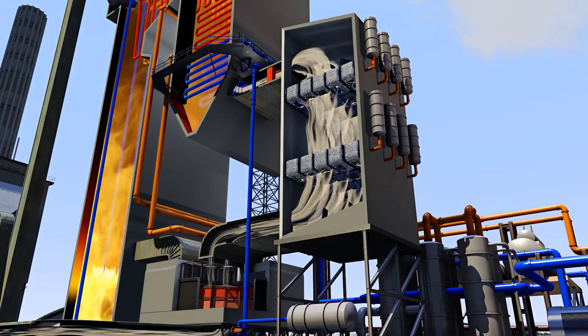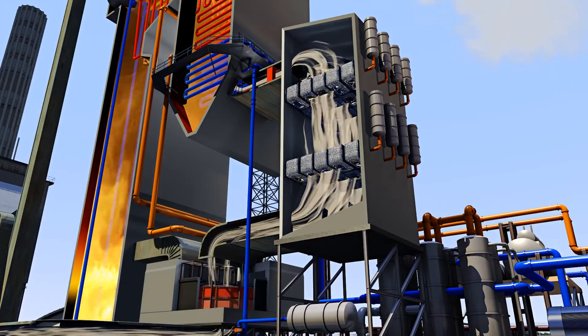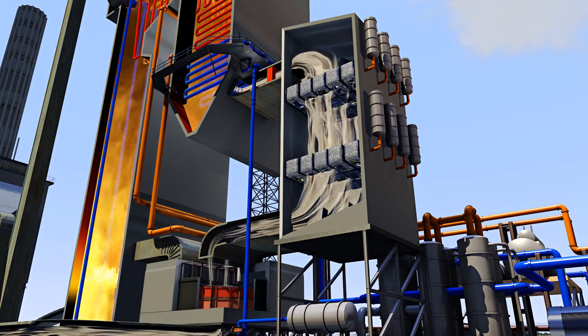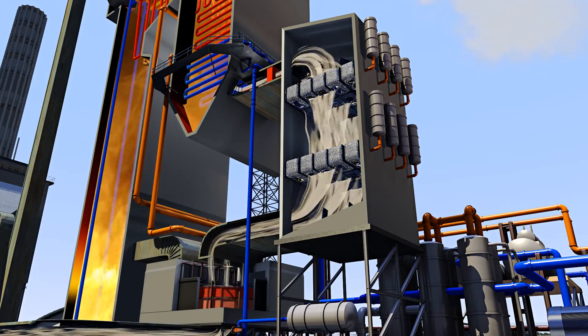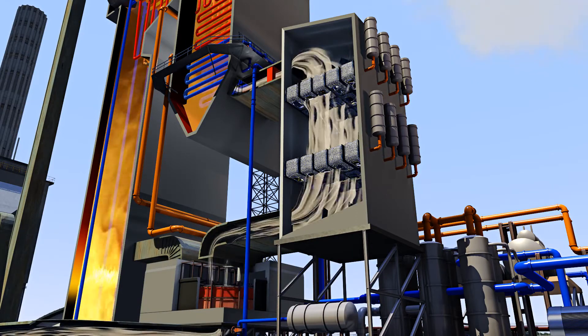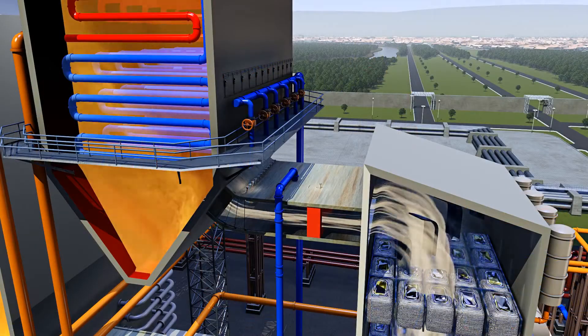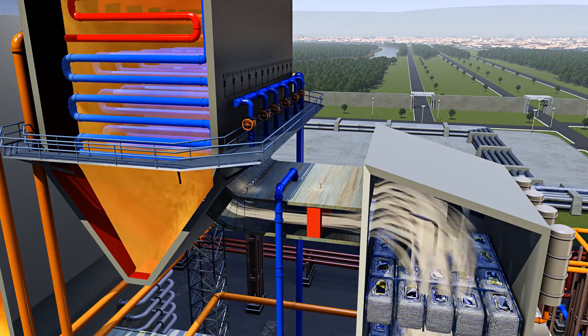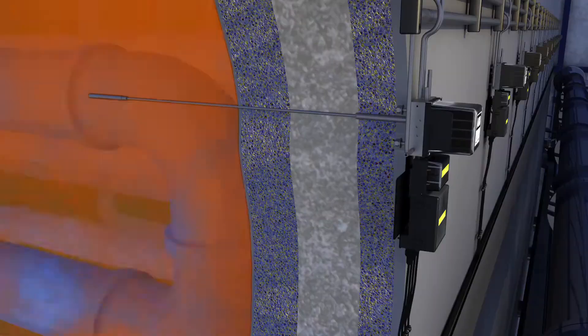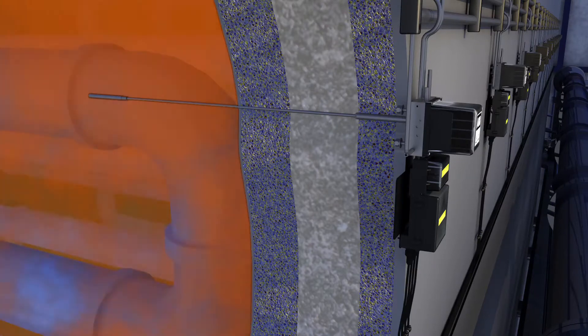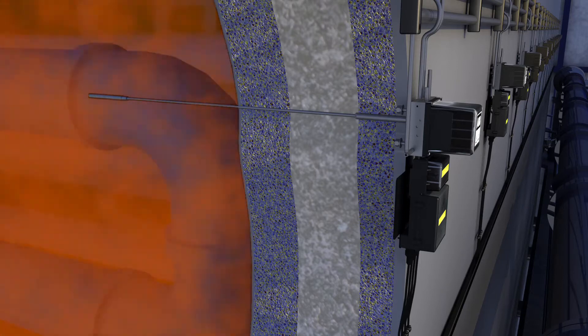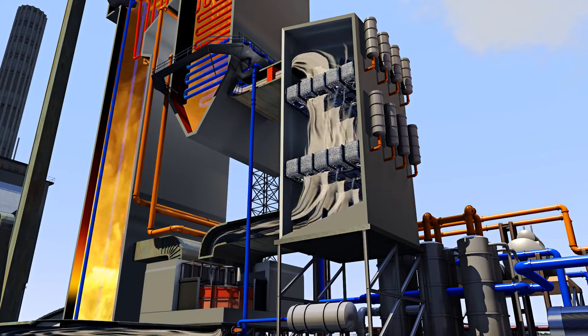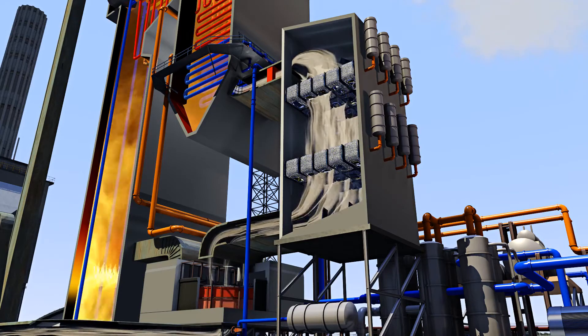Maximising the efficiency of the combustion process to ensure the optimum level of excess air will help to minimise the load on these plants. Both thermal and fuel NOx levels can be controlled by using oxygen probes to ensure the excess air level does not exceed the required limit. Measuring the flue gas at the economiser outlet will enable operators to assess the effectiveness of the air-to-fuel mix in the combustion process, which can be fine-tuned if too much air is present.